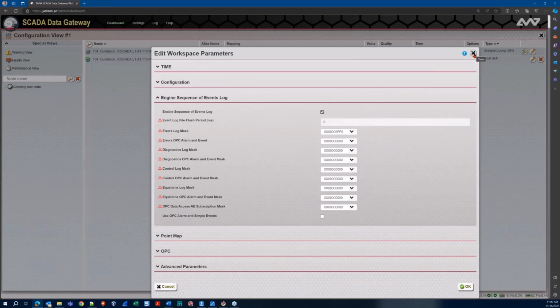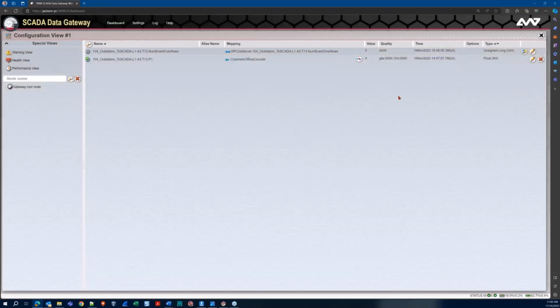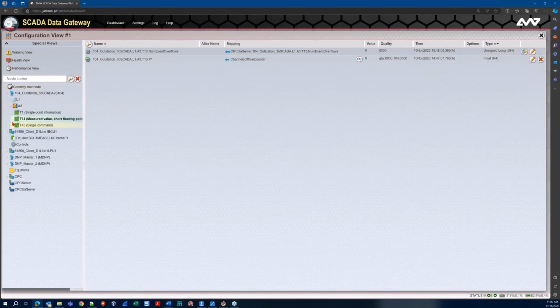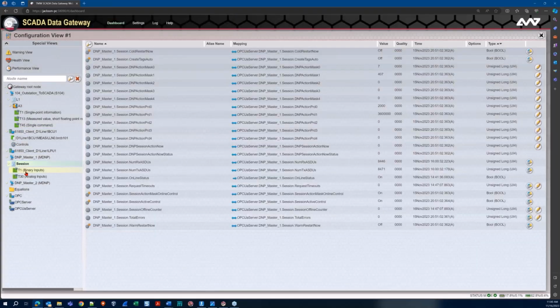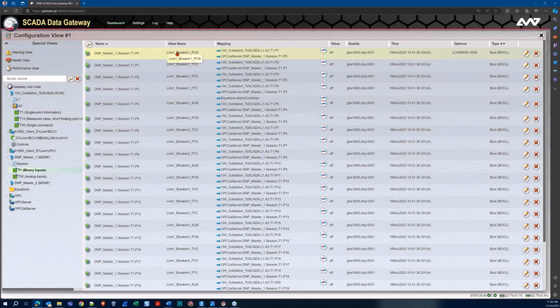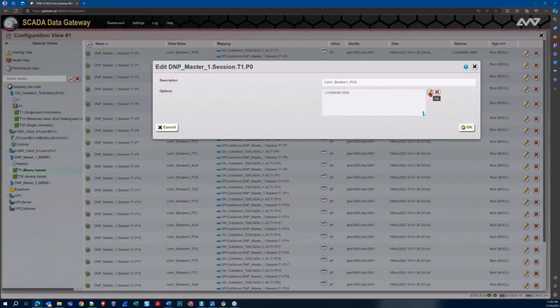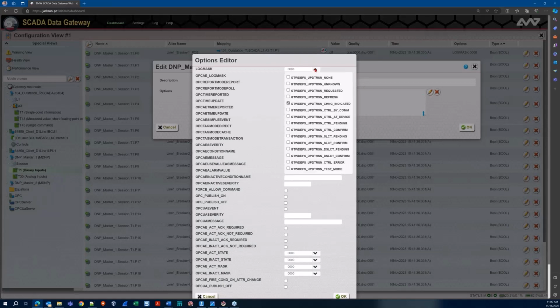Let's say I didn't want to do it at a global level, and I was really only interested in capturing individual points and their changes in my sequence of events log. I do have that option for that granularity as well. So coming back down to, for example, this DNP point, let's say I wanted to trigger a recording every time the breaker position changed. I could come over here, click my pencil to edit this particular point, click on the pencil again to get to the options, and we'll see that I actually already have that setting turned on.